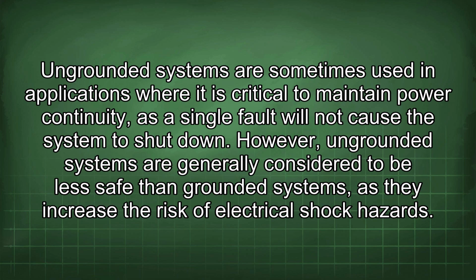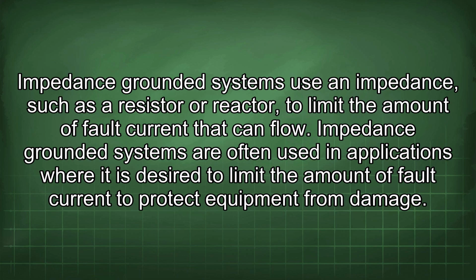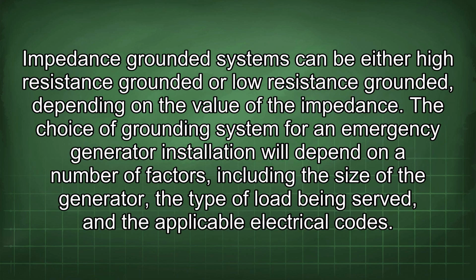Impedance grounded systems use an impedance such as a resistor or reactor to limit the amount of fault current that can flow. Impedance grounded systems are often used in applications where it is desired to limit the amount of fault current to protect equipment from damage. Impedance grounded systems can be either high resistance grounded or low resistance grounded, depending on the value of the impedance.